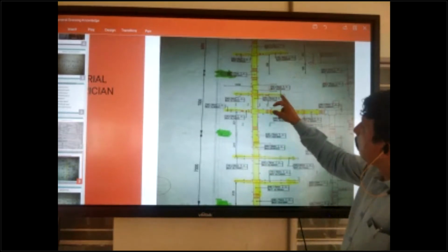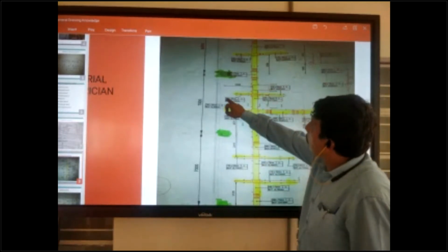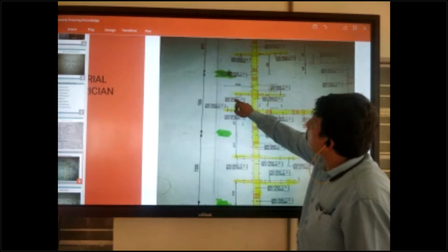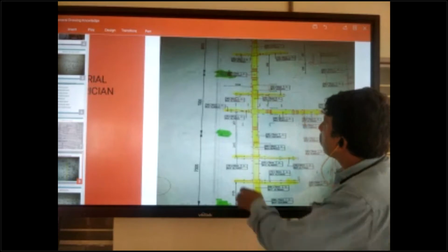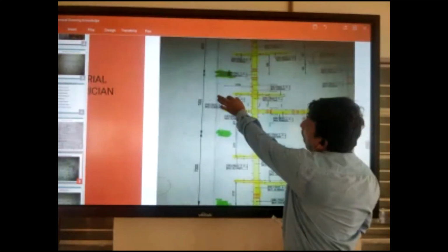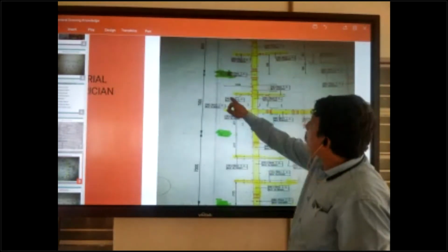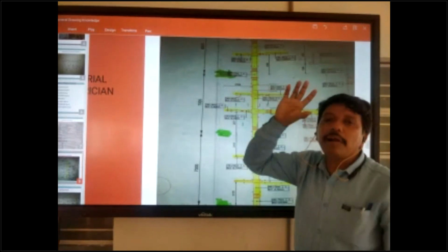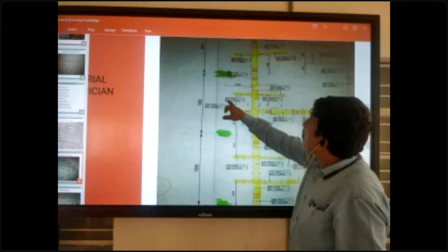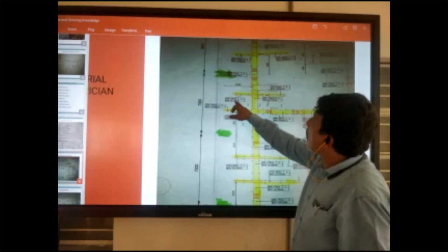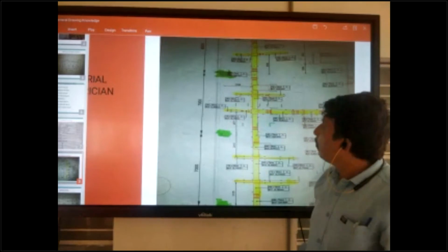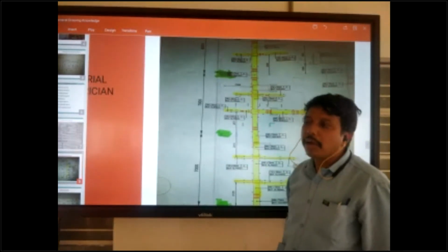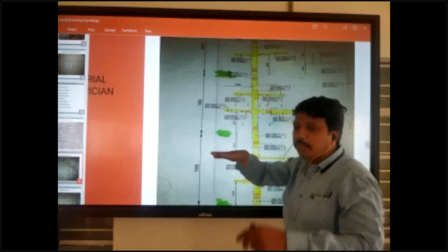Okay. First, you can check the cable tray size. At the front there is written 150 into 50 mm square. This means the cable tray size is written on the upper side: 150 into 50 mm square. So this means the cable tray size. And BOT plus 3726 mm. What is the meaning of BOT? Bottom of the cable tray. Bottom of the cable tray.